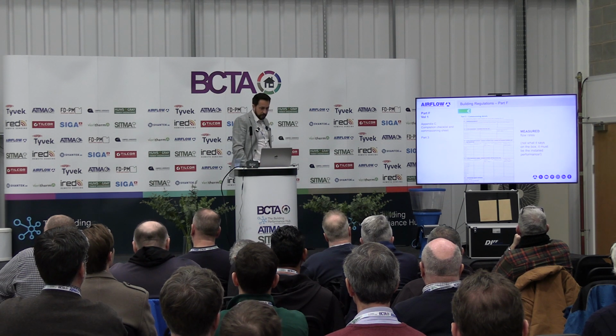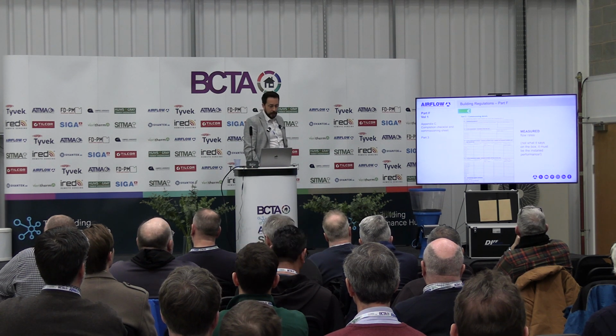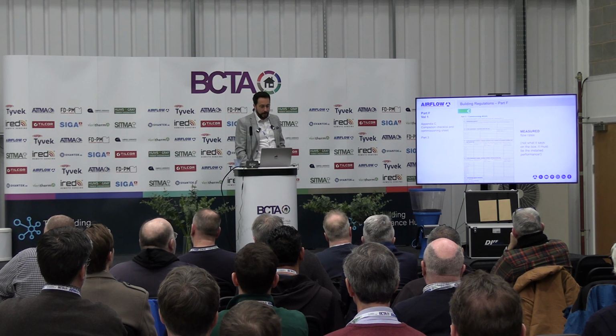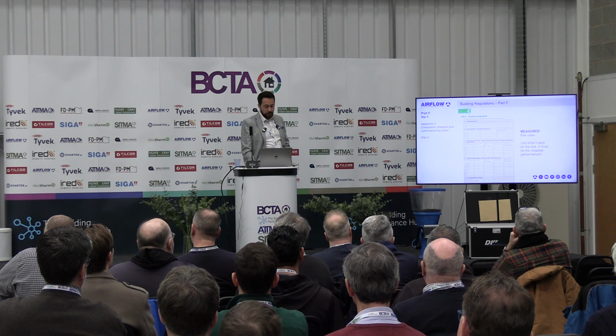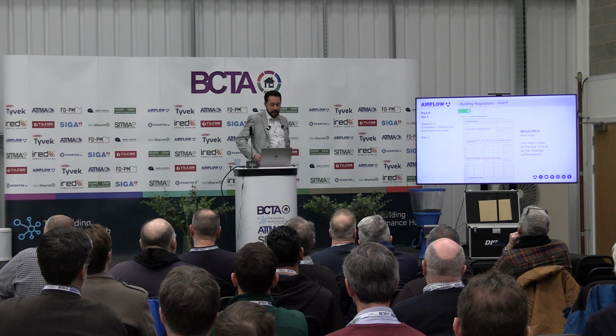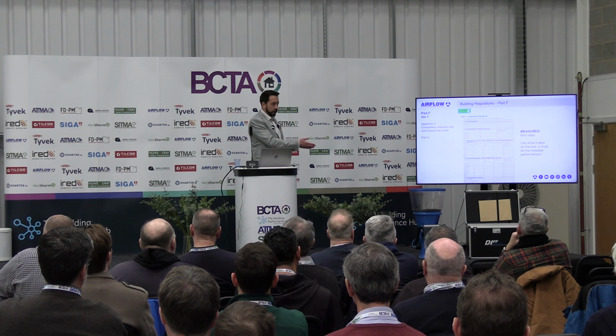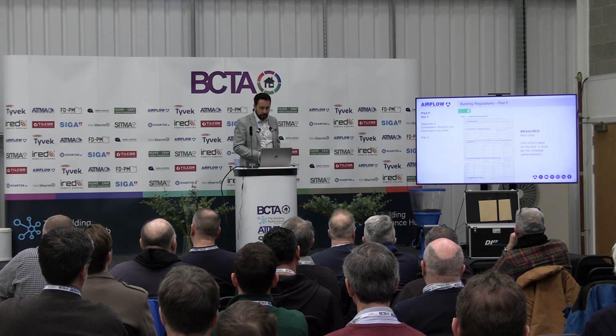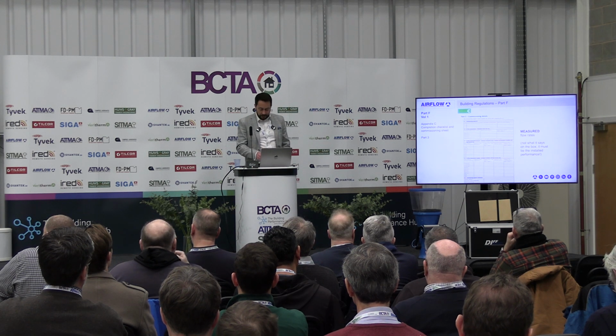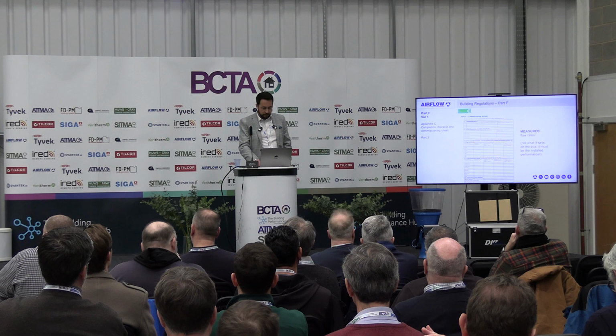Also in Part F at the back, in Appendix C, there's a completion checklist and commissioning sheet. And again, this is the measured flow rates. So the installer has to put here the actual flow rates when they've used a measurement device to measure the flow rates. So again, not just what it says on the box, it has to be the performance.